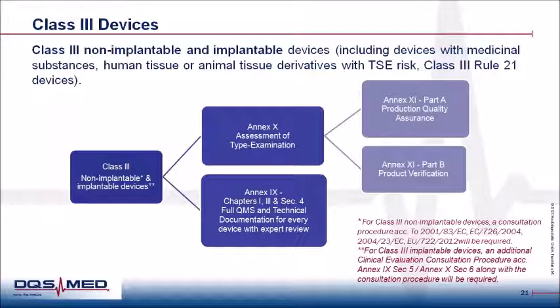is a viable option. A certificate will be issued following a notified body quality management audit, and a second certificate will be issued for every device after the review of the associated technical documentation is approved. It should be noted that manufacturers for Class 3 medical devices also have an additional option to pursue Annex 10 type examination in combination with Annex 11 Part A or Part B, and therefore with a QMS focused on production and control. But for Class 3 devices, there are 2 additional steps before a CE certificate can be issued.